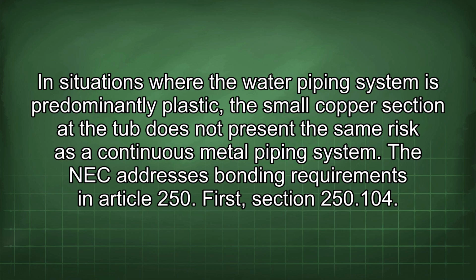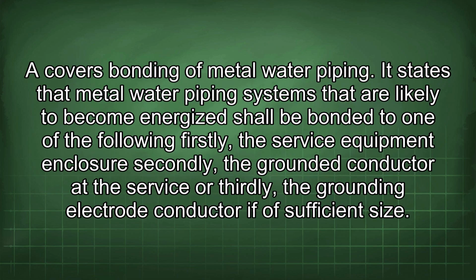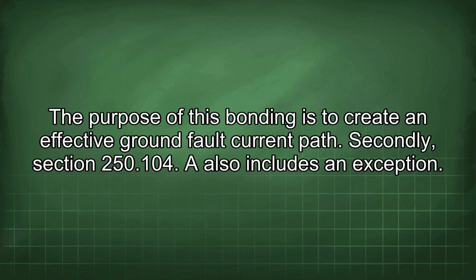The NEC addresses bonding requirements in Article 250. First, Section 250.104 covers bonding of metal water piping. It states that metal water piping systems that are likely to become energized shall be bonded to one of the following: firstly, the service equipment enclosure; secondly, the grounded conductor of the service; or thirdly, the grounding electrode conductor if of sufficient size. The purpose of this bonding is to create an effective ground fault current path.